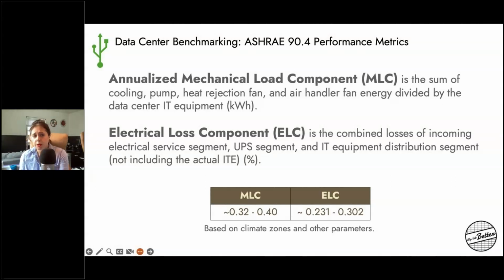Then you also have your ELC, or electrical loss component. This looks at the electricity coming into the facility before going into the servers. It doesn't take into consideration losses in the server energy, but rather the energy coming through your transformers, your PDUs, which we'll get into a bit more later, and your UPSs, or uninterruptible power supplies.